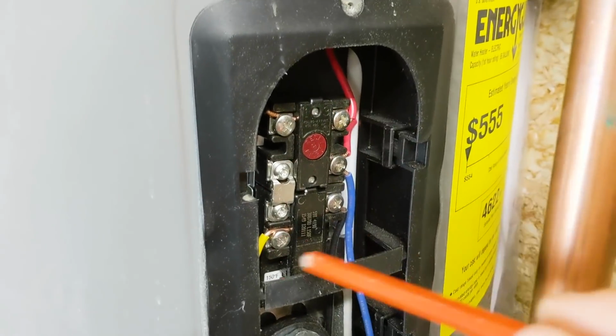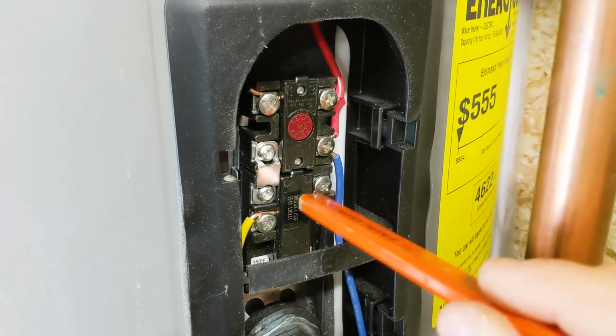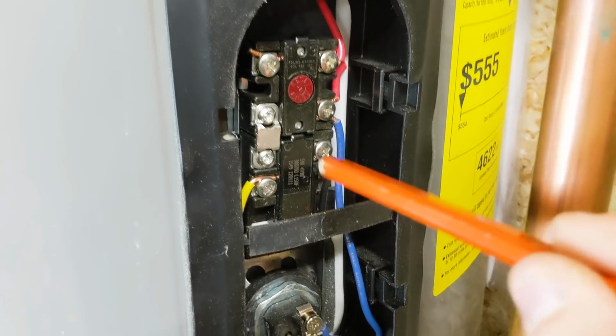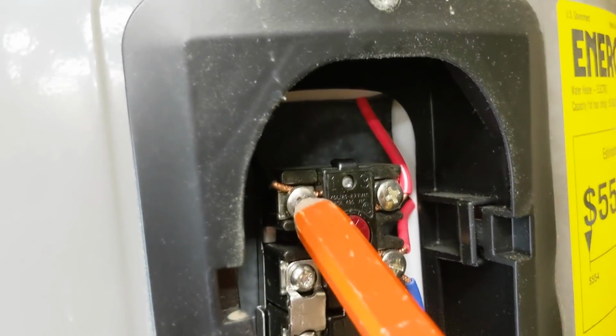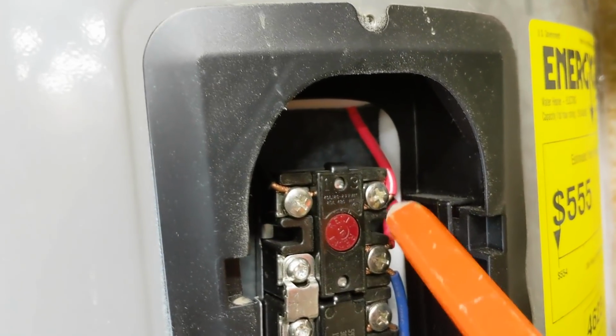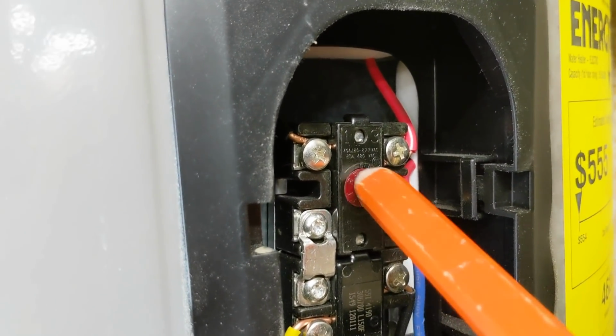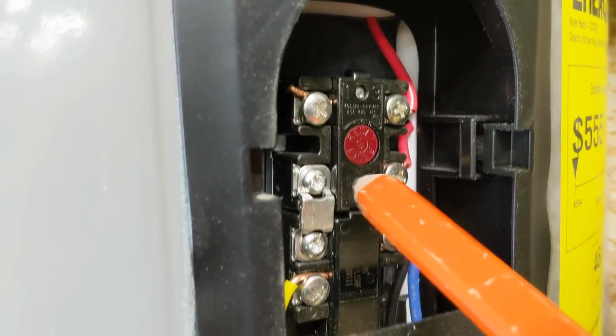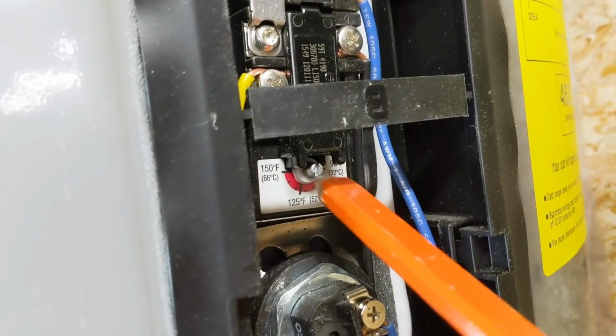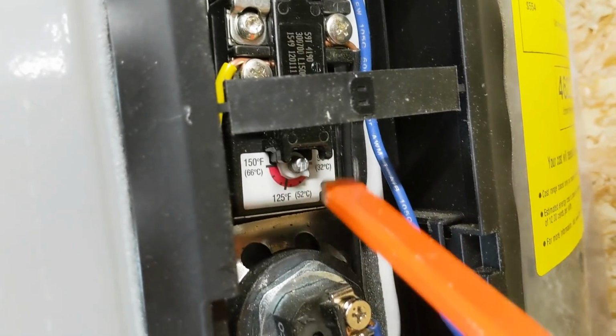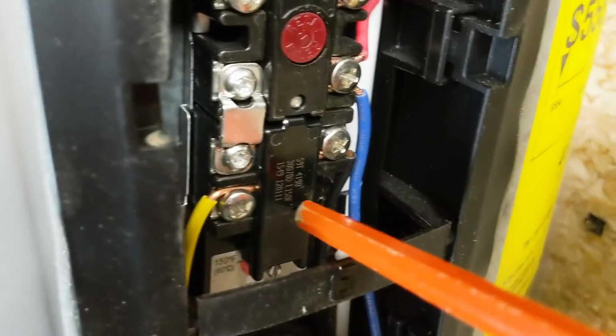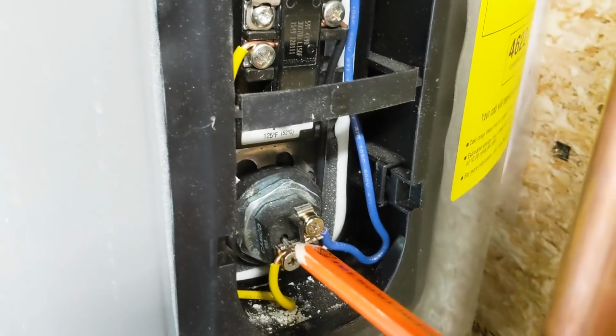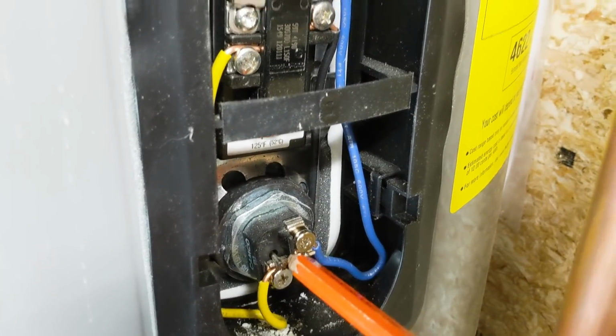Now keep in mind, all of this wiring is exactly straight from the factory. I have never touched this. The power comes in at the top of the water heater, travels down on these two wires, so we have L1 and L2. These are two hot legs. This is a thermal overload switch, and it can be reset. Then the power goes to the thermostat, which is this one right here, and you can dial it in to whatever temperature you want. If this top heating element says that it's satisfied, it does not send the power to this thermostat. Instead, it redirects the power down.